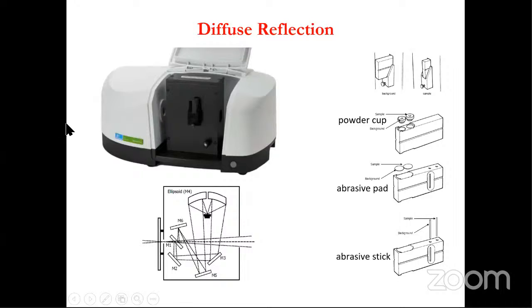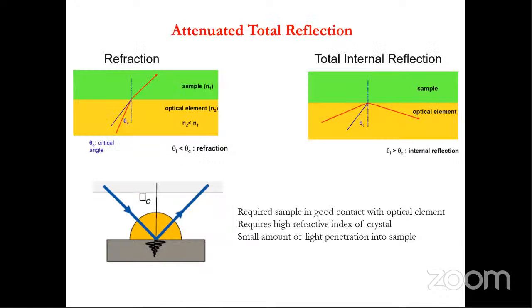So this is a machine where we do diffuse reflectance. It has two to three types of cup: a powder cup, an abrasive pad, and an abrasive stick, where we can put on the sample and see diffuse reflectance. ATR is basically total internal reflection. It requires the sample to be in good contact with the optical element, and it requires a high refractive index of the crystal and a small amount of light penetration into the sample. So this is a key thing which we do.